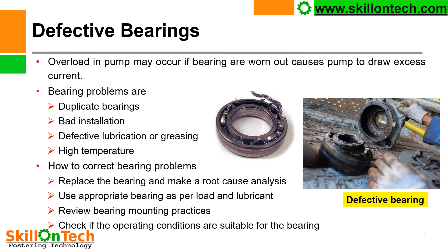Defective bearings — you can see a picture of defective bearings here. Overload in a pump may occur if bearings are worn out, causing the pump to draw excess current. Bearing problems include: duplicate bearings, bad installation of bearings, defective lubrication or greasing, and high temperature. To correct bearing problems: replace the bearing and perform root cause analysis; use appropriate bearings as per load and lubricants; review bearing mounting practices and adopt correct practices; check that operating conditions are suitable for the bearing; and ensure proper lubrication and that bearing temperature does not exceed limits.